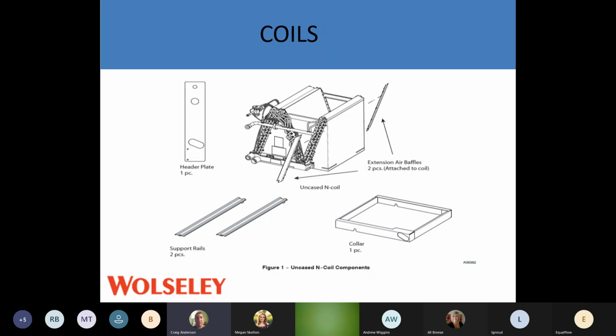N coil, if you haven't installed one, you have to be very mindful when installing the N coil. The N coil has two parts on it. One part where the A is, and then another small part where the N part is on the right-hand side. Probably a dozen calls a year or maybe more: unit is freezing up, we have no idea why. On the right side of this coil, we only have about 1.5 inches of gap. If you install it like a typical A coil, put your channels in, 1.5 inches on each side, slide the coil in, chances are you're going to block off that right side of the coil.